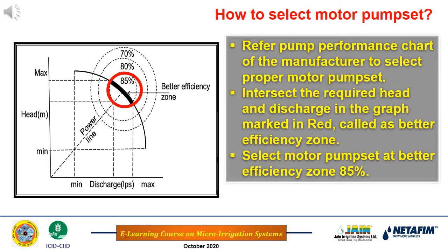How to select motor pump set? Refer pump performance chart of manufacturer to select proper motor pump set. Intersect the required head and discharge in the graph marked in red, called as better efficiency zone. Select motor pump set at better efficiency zone 85%.